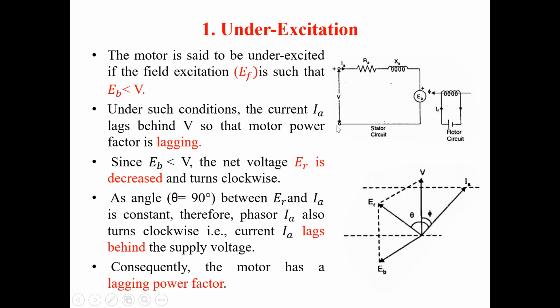If we change excitation, there are various stages of operation of the synchronous motor, one of which is under-excitation, when Eb is less than the input voltage. That stage is known as under-excitation, and the power factor at that time remains lagging in nature, meaning the current drawn from the supply is lagging.